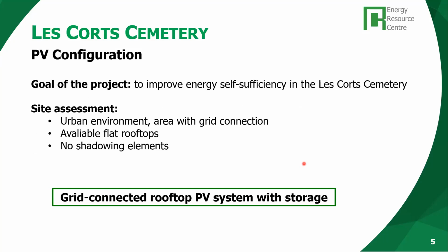This photovoltaic installation is a type of installation called grid assisted. And this means that it has the grid as a support system. But the photovoltaic installation and the grid can never work in parallel because it was not legal. The consumptions are fed either from the photovoltaic installation or from the grid. The system has a switch that is in charge of commuting between one system or the other.